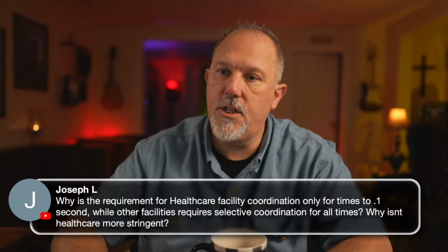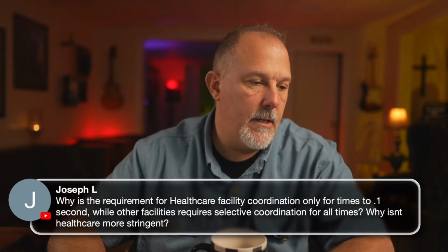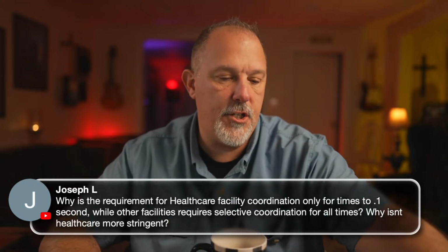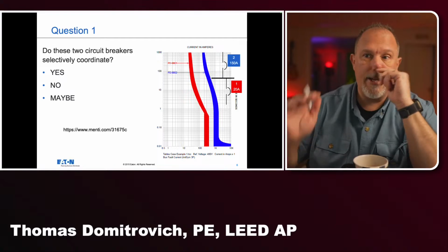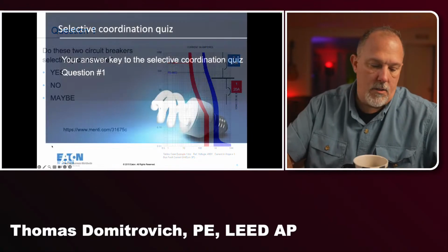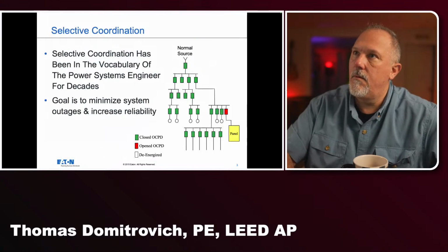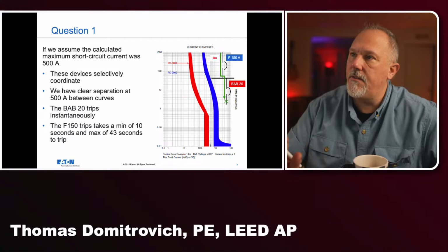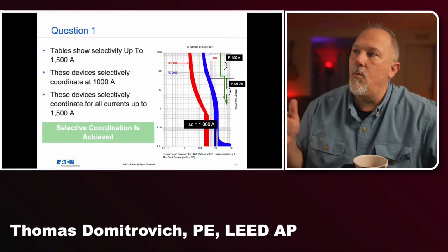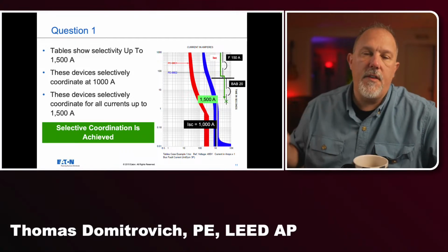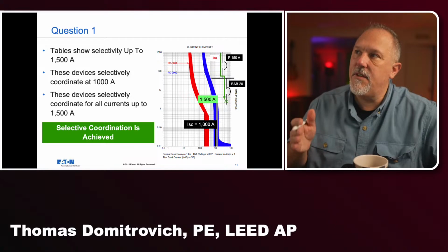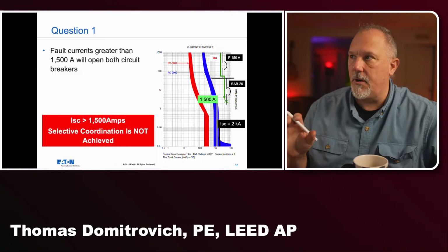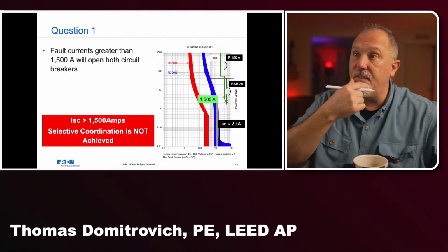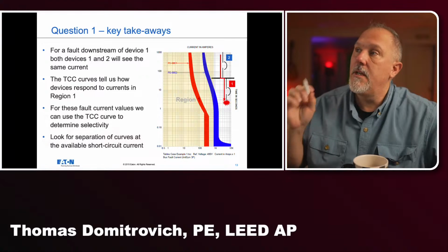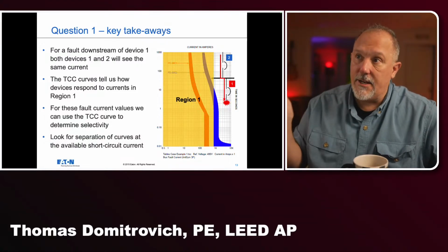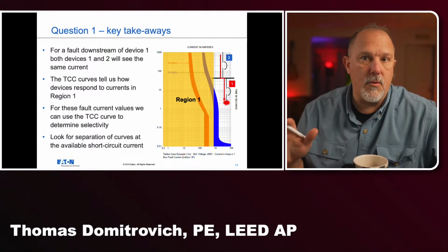Remember when I showed this, and I said we don't know whether or not, we said we need to know what the available fault current is. If the fault currents are high enough, then both are going to open. So you have to compare the TCC curves with the available fault currents, right? So if the available fault current is greater than 1500 amps, you do not have selective coordination. So all currents less than that, in region 1, will selectively coordinate.